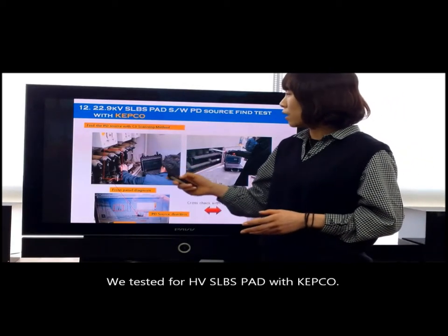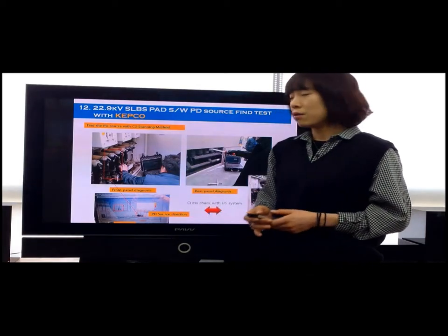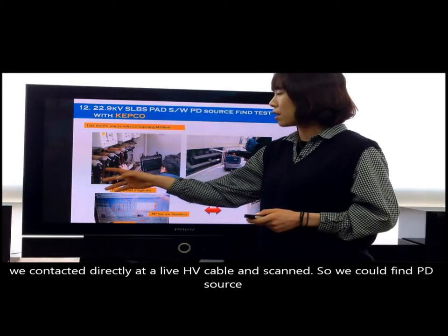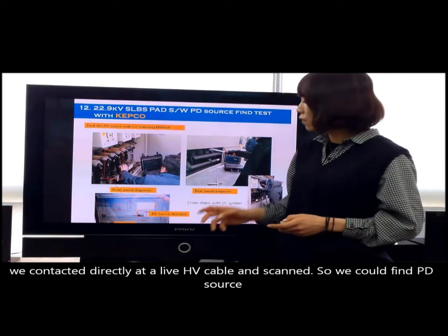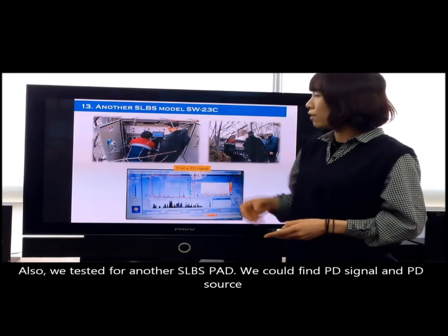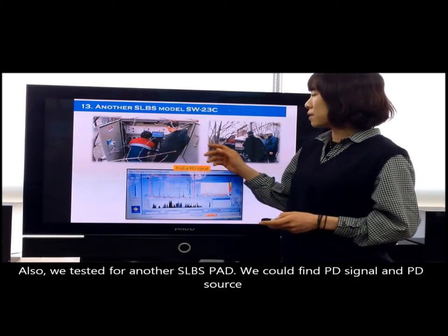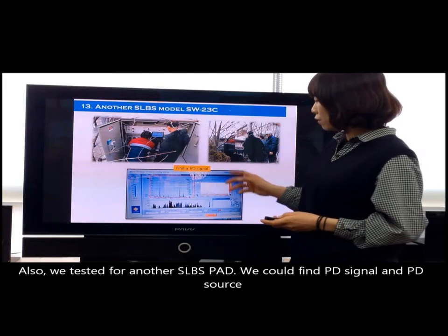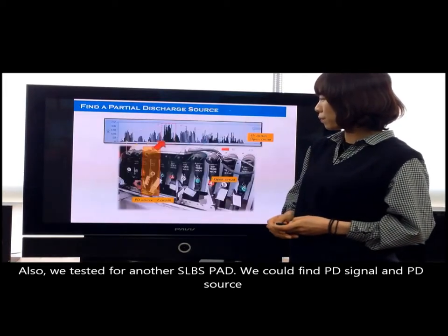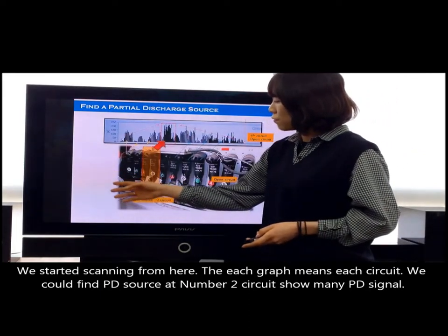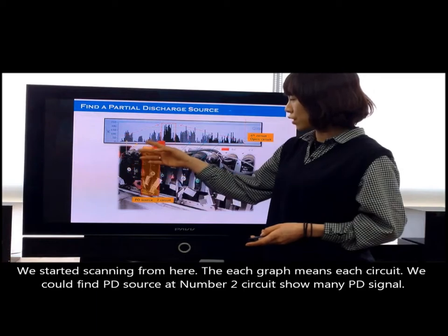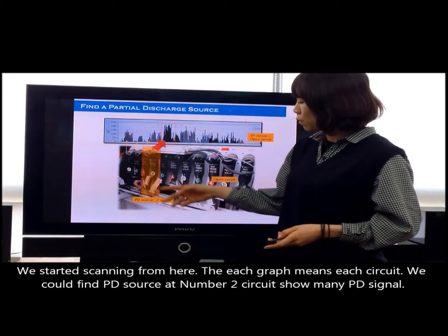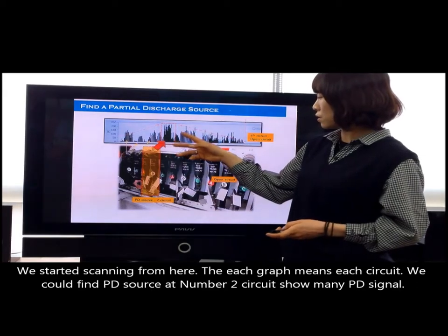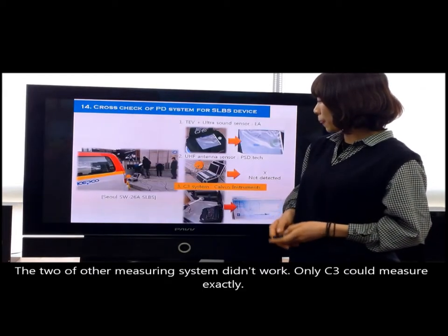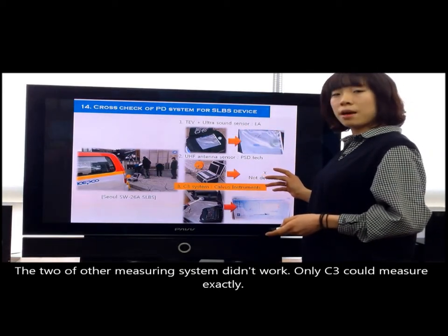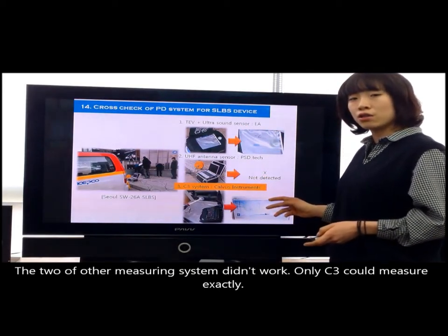We tested a high voltage SLBS pad with KEPCO. We contacted directly at a live high voltage cable and scanned, so we could find the PD source. And also, we tested another SLBS pad, and we could find the PD signal and PD source. We started scanning from here, and each graph means each circuit. We could find the PD source at number 2 circuit showing many PD signals. The two other companies' measuring systems didn't work. Only C3 could measure exactly.